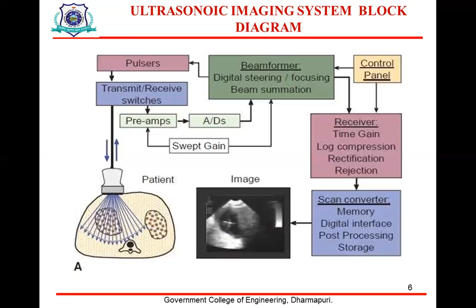In image data acquisition, the images are created using the pulse echo mode format of ultrasound production and detection. Each pulse is directly transmitted into the patient, and the partial reflection from tissue interfaces creates echoes which return to the transducer. Image formation using the pulse echo approach requires a number of hardware components. The first one, beamformer.